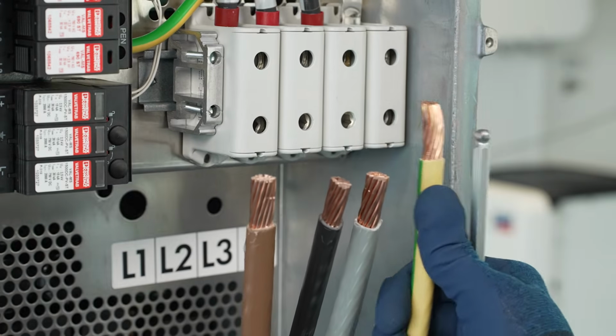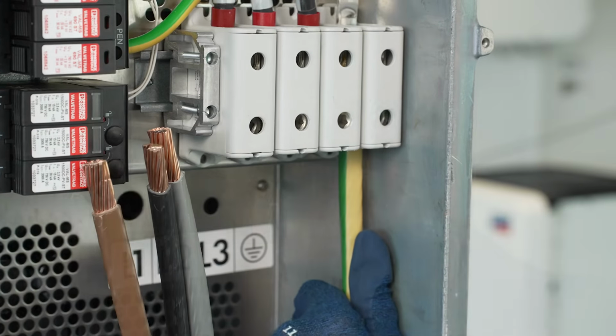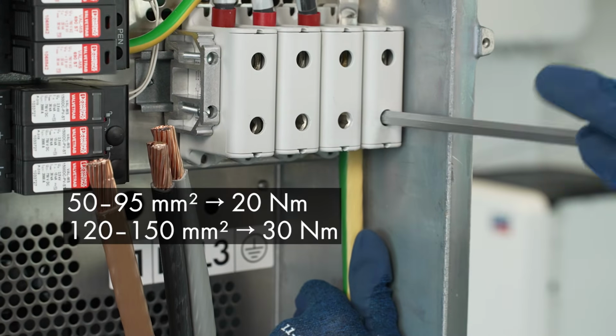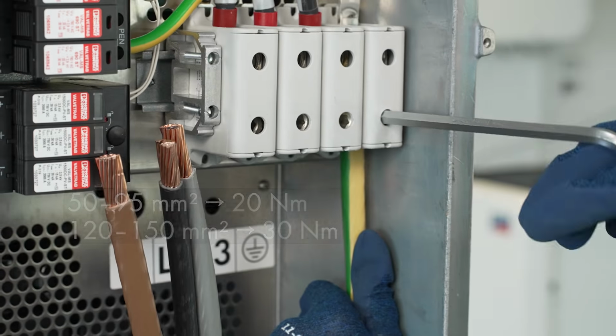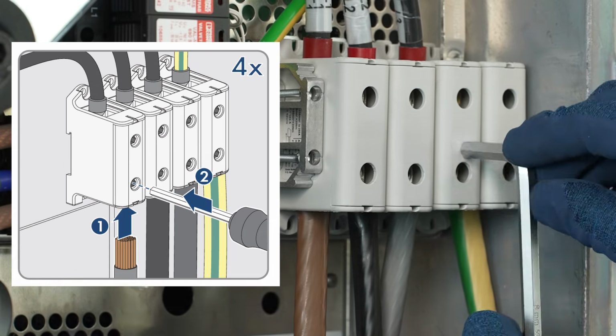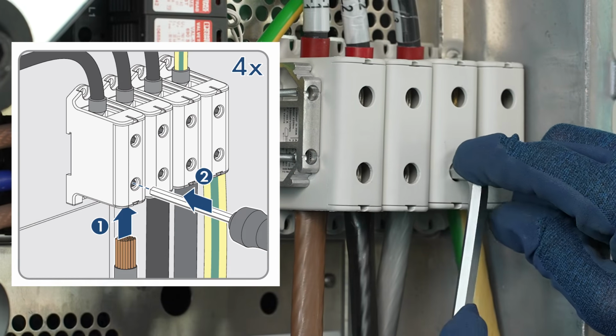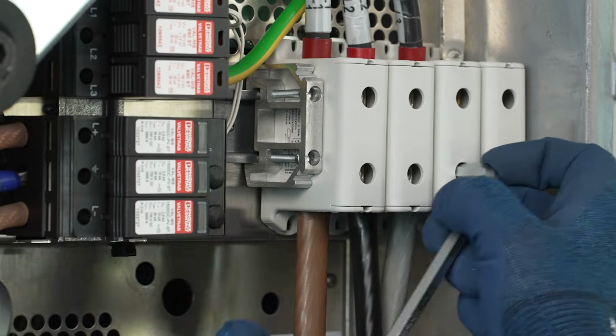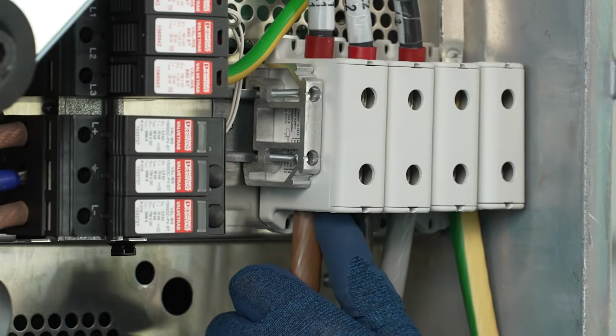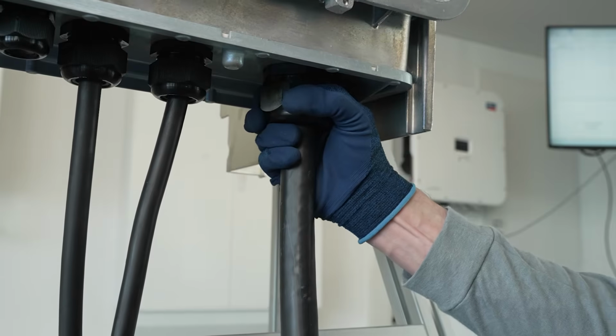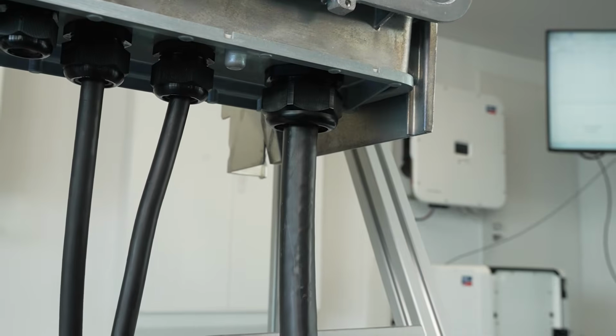Now we connect the PE, L1, L2, and L3 conductors to the terminal blocks according to the labeling. We insert each conductor fully into its respective terminal and then tighten the screws. Afterwards, we check the correct assignment and secure fit of all conductors. Finally, we tighten the lock nut on the cable glands.